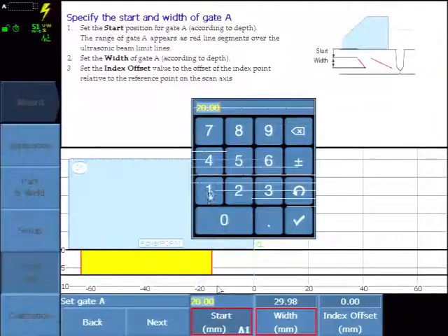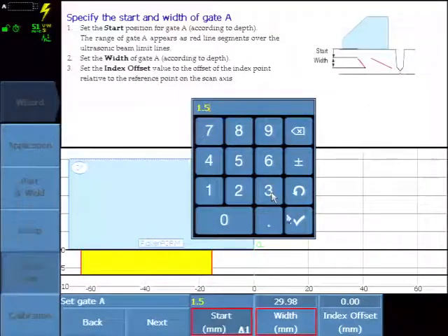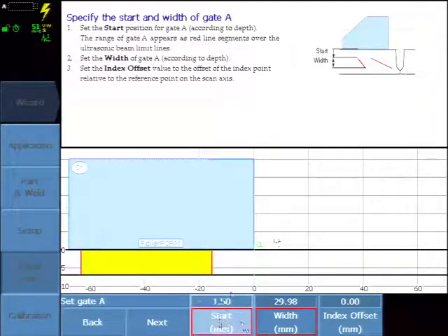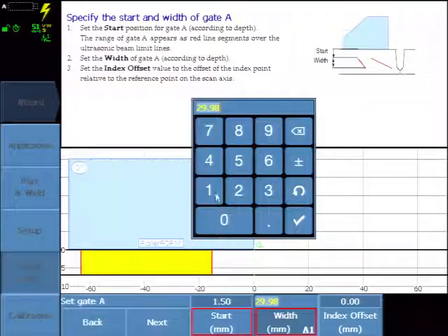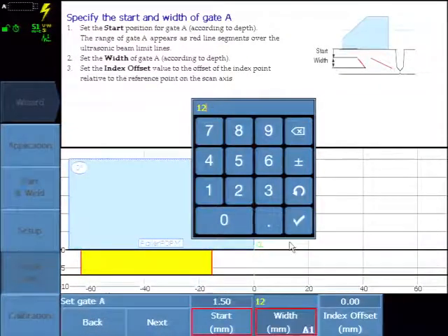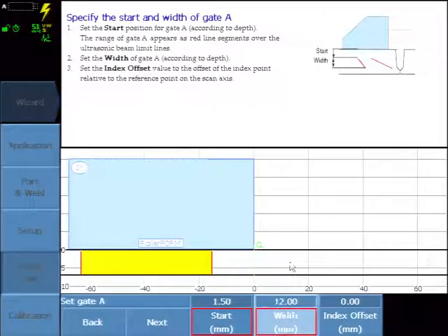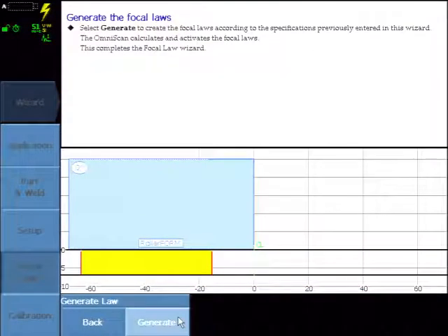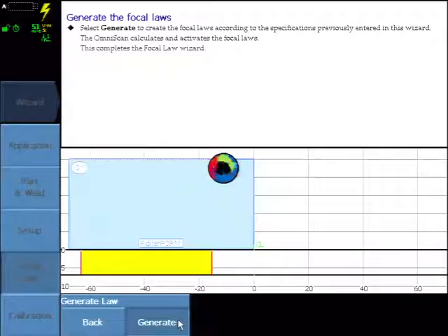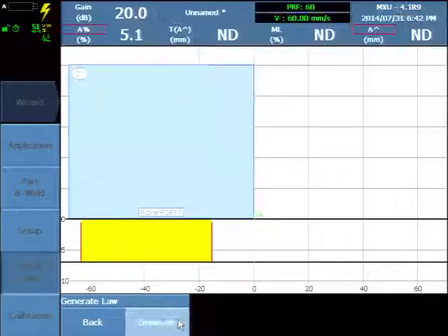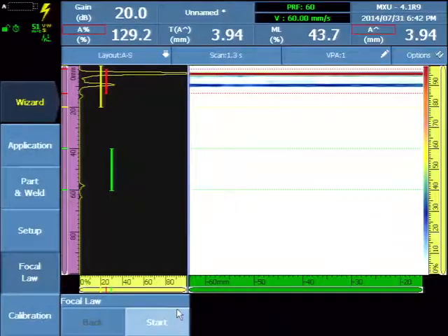Enter gate A position to start at about 1.5 to 2 mm. We want the gate to be as close to the surface interface signal as possible and we'll adjust this during our UT optimization. So at this point the group and all of the focal laws have been created.